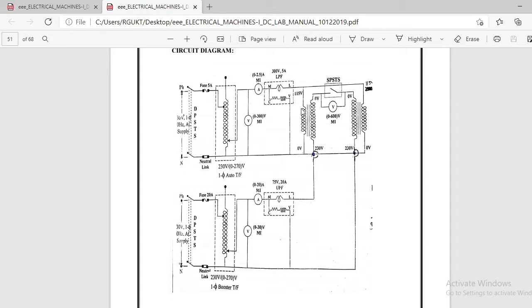Next, coming to this wattmeter, LPF. This is an LPF wattmeter. Why are we using this? In order to measure the iron losses of both the transformers. Why do we need to use only an LPF wattmeter? Because under this condition the circuit is at no load, and under no load it acts as purely inductive. For an inductive circuit, if you want to measure the power, we need to use the LPF wattmeter only.